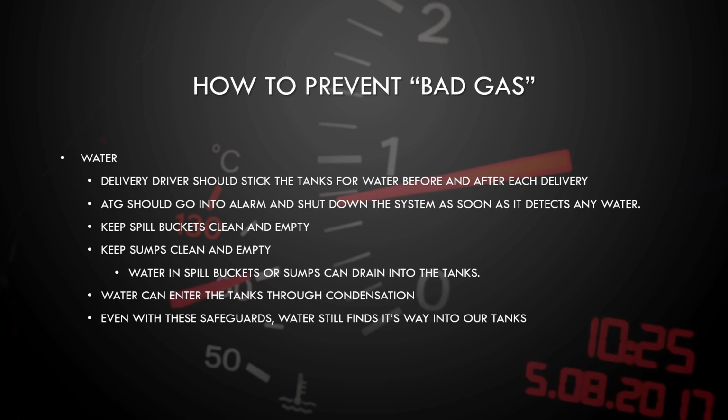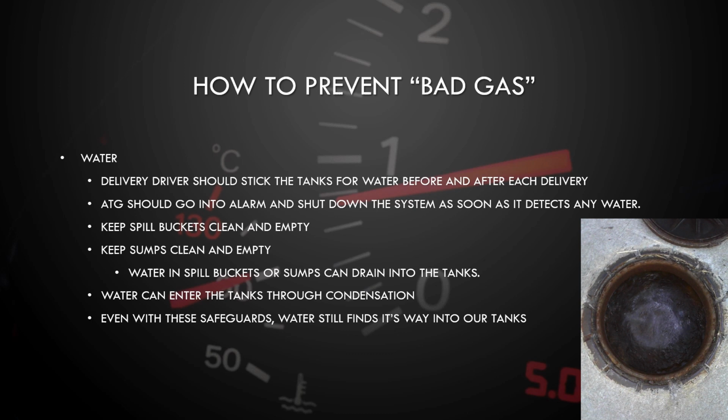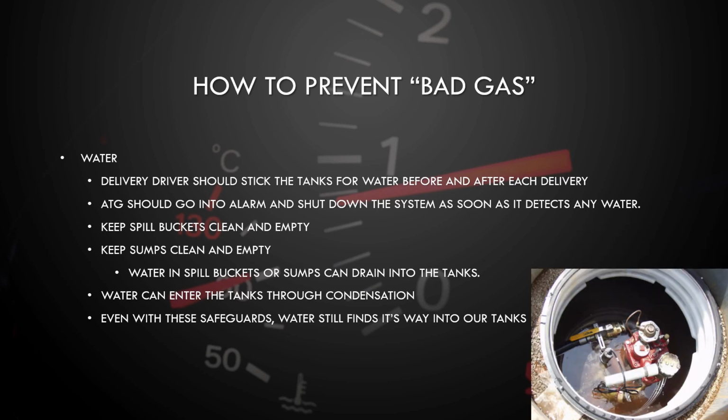Our Veeder-Root ATG should go into alarm and shut down the system as soon as it detects any water. We need to keep our spill buckets empty. We need to keep our sumps clean and empty, because if we allow those to fill up with water, it could eventually drain into your tanks.